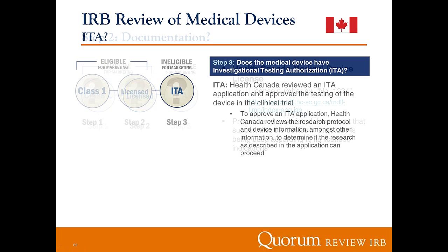Finally, if the device is not eligible for marketing in Canada, as in it's not Class 1 and it's not licensed by Health Canada, it can still be used in a clinical trial, but the documentation that you need to make sure it can be used in a clinical trial population is an ITA, otherwise known as an Investigational Testing Authorization. So Health Canada will issue an Investigational Testing Authorization after Health Canada reviews the research protocol and device information, amongst other information, and determines that the research as described in the application can proceed. This is similar to the FDA IDE process.